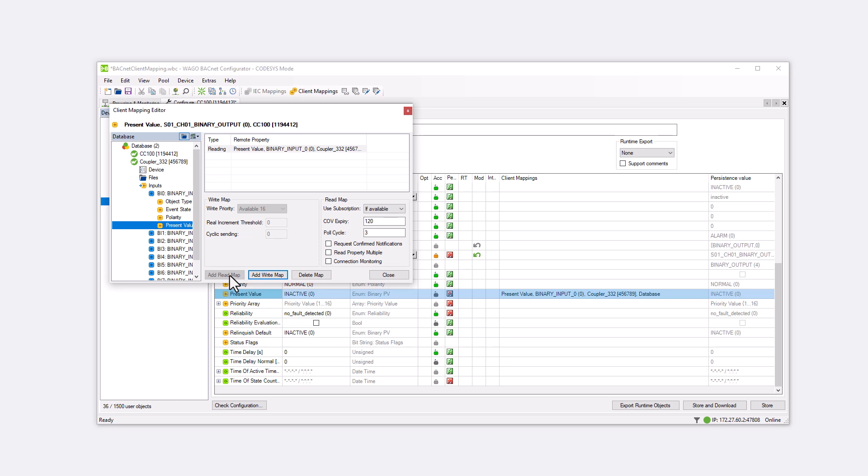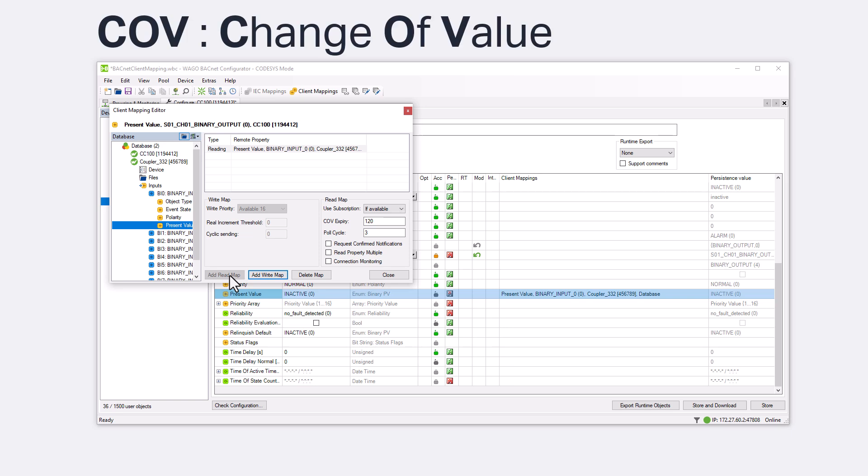Now we can configure a few settings. In the right area are the Read Map settings. There are two different ways to query the value. One option is COV, which stands for Change of Value. When the value changes, the server notifies the client and the client reads the value. This method has the advantage of only using bus bandwidth and controller computing power when relevant data is available.